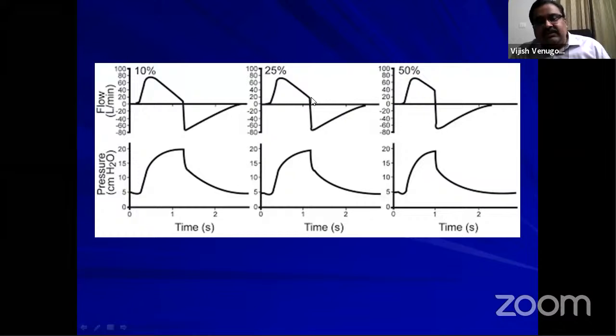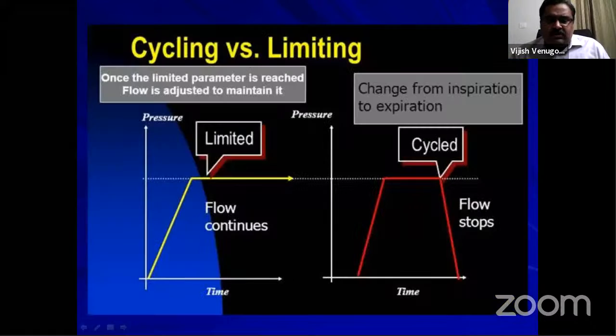Here you can see at 25%, it means only 25% of your flow is remaining. So at that time, it will trigger into expiration. So that is flow cycling. Here again, at the end of 50%, it is triggering. So this is flow cycling. So what is the difference between cycling and limiting or targeting? Once the limited parameter is reached, flow is adjusted to maintain it. That means flow is continuing at the limit. So this is the major difference between cycling and limiting.